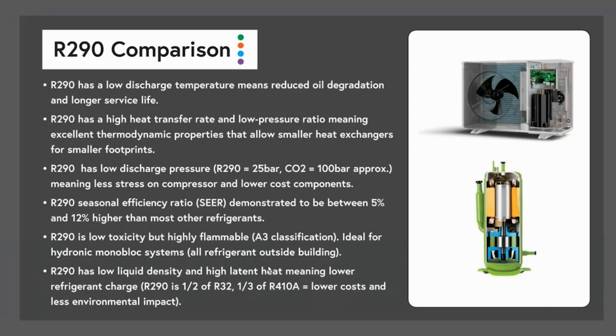So there was a lot of reluctance to bring R290 into the space for home heating. The reason for that is that when it was being considered many, many years ago, basically in all the appliances on the market, the refrigerant travelled into the building. The outside unit was a split, and the refrigerant went into the building through to the fan coil units or whatever system was being used for heat distribution. And there was no way they wanted something with this sort of classification inside the building envelope. However, what's happened is that the regulations have basically pushed the refrigerants out of the buildings. And this unit that we're talking about today is a monoblock, so it has all the refrigerant contained in the outside unit, and therefore there is no issue with that.